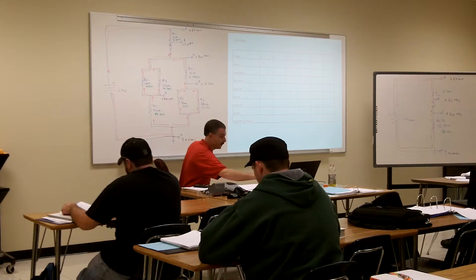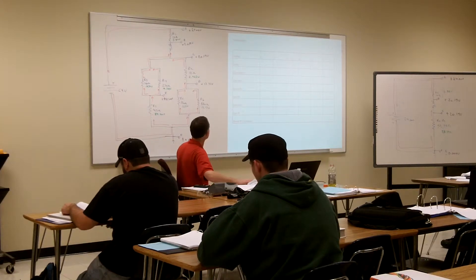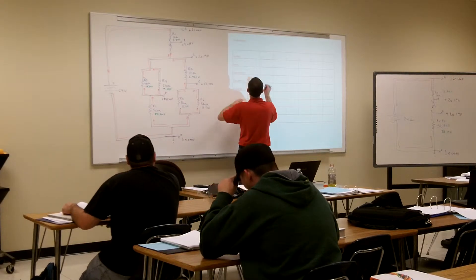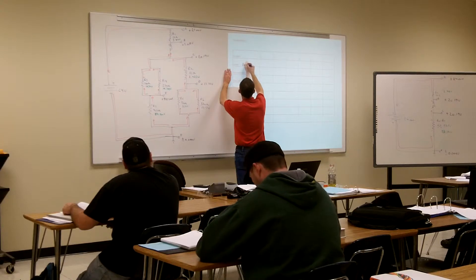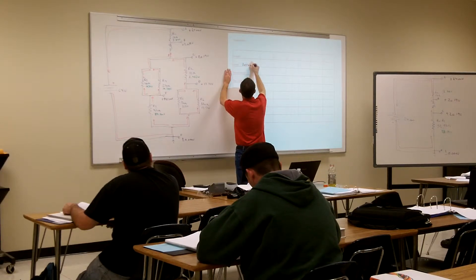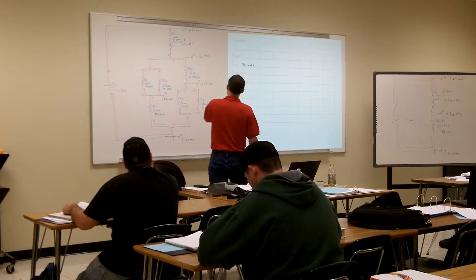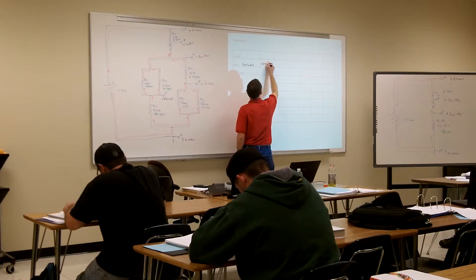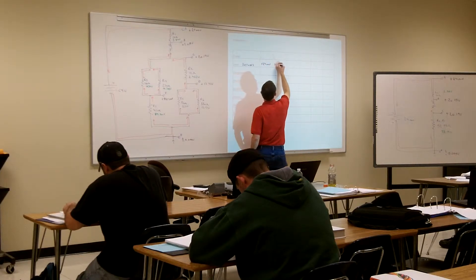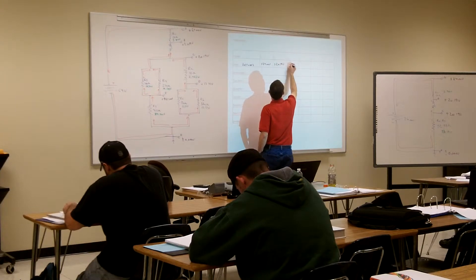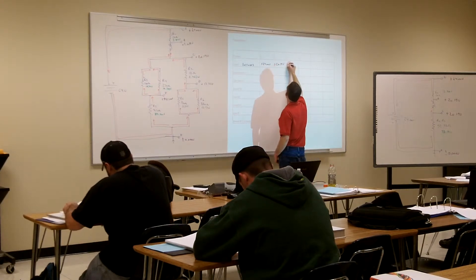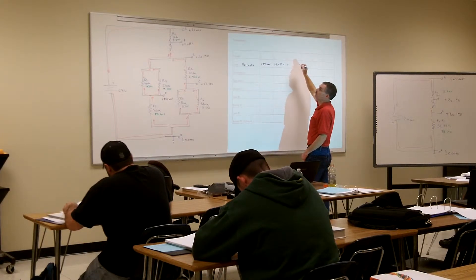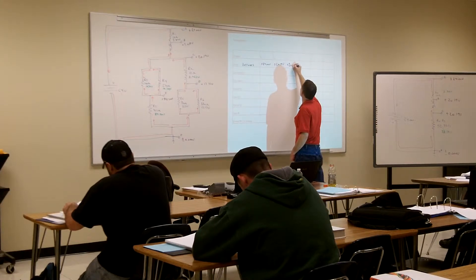With my normal circuit, we're going to put in our voltages for our test points so we can see what's going on. What do I get on a normal circuit? Test point A: plus 24 volts. Test point B: plus 20.19 volts. Test point C: plus 17.77 volts. Also 20.19 volts at that point.